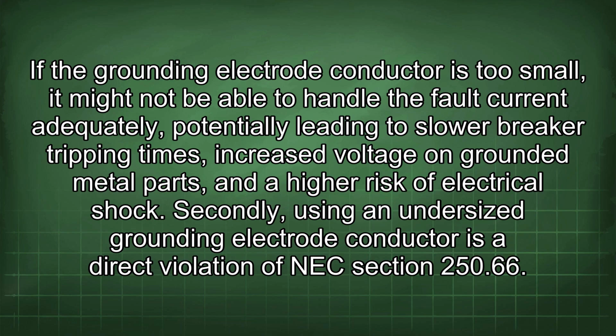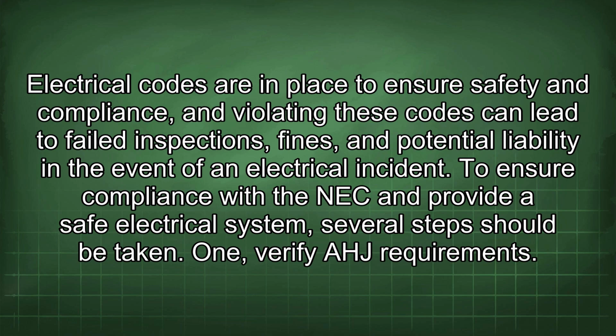Secondly, using an undersized grounding electrode conductor is a direct violation of NEC section 250.66. Electrical codes are in place to ensure safety and compliance, and violating these codes can lead to failed inspections, fines, and potential liability in the event of an electrical incident. To ensure compliance with the NEC and provide a safe electrical system, several steps should be taken.